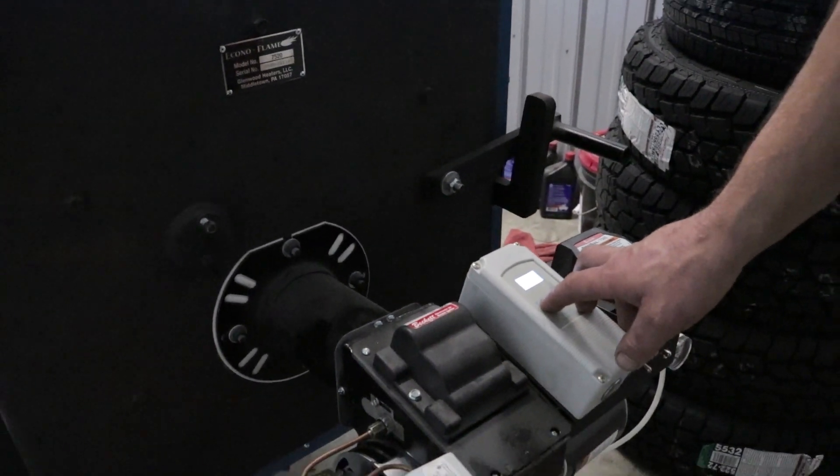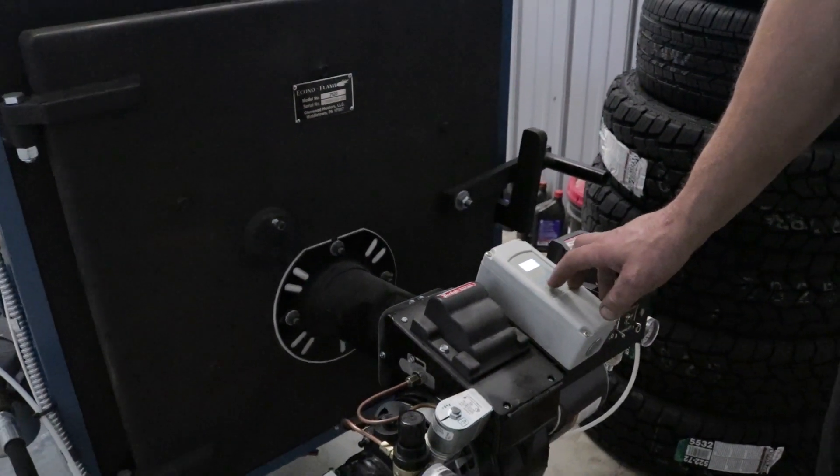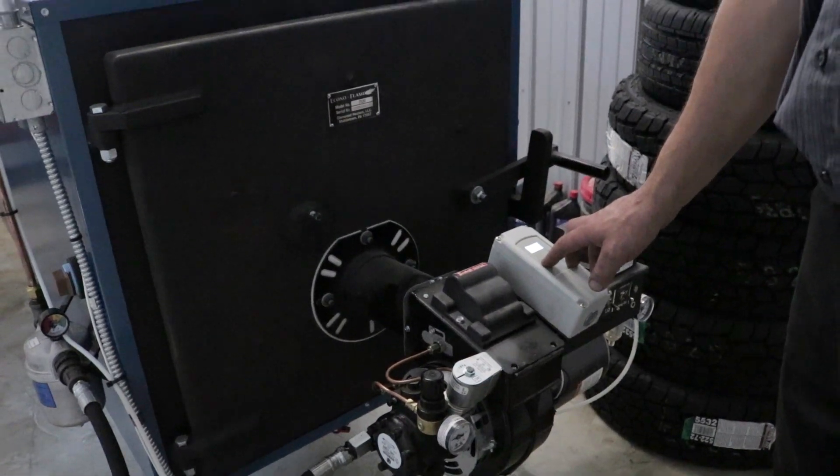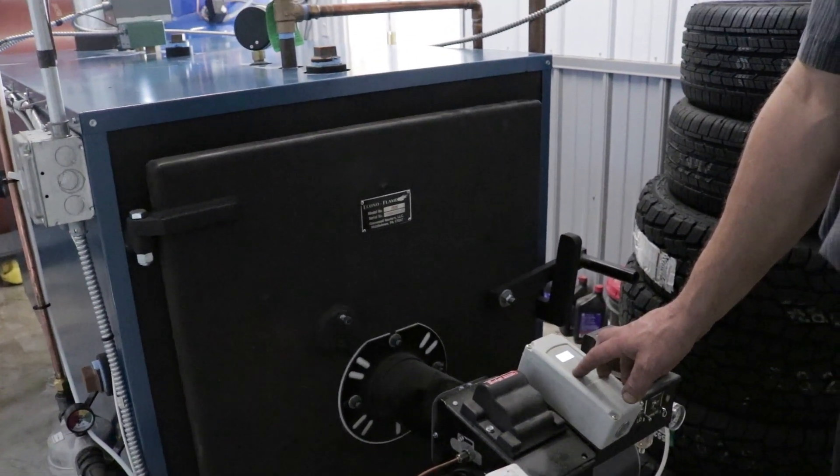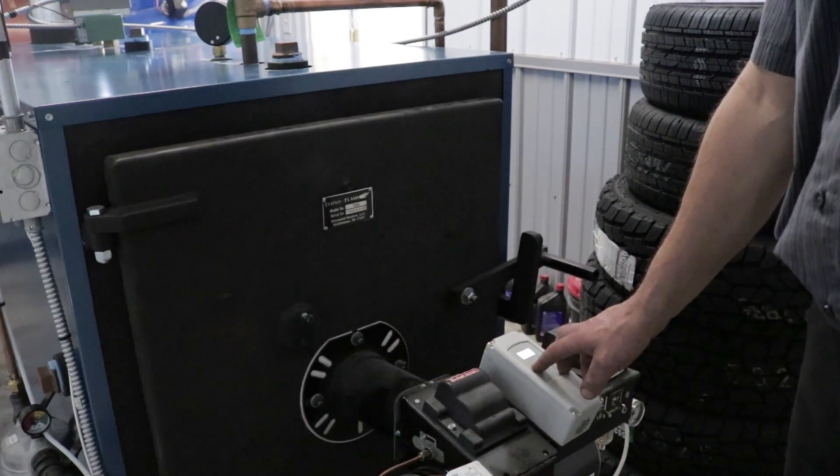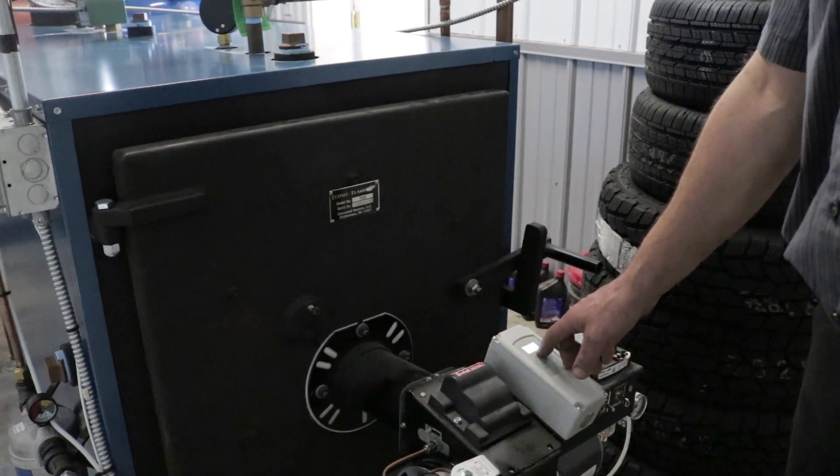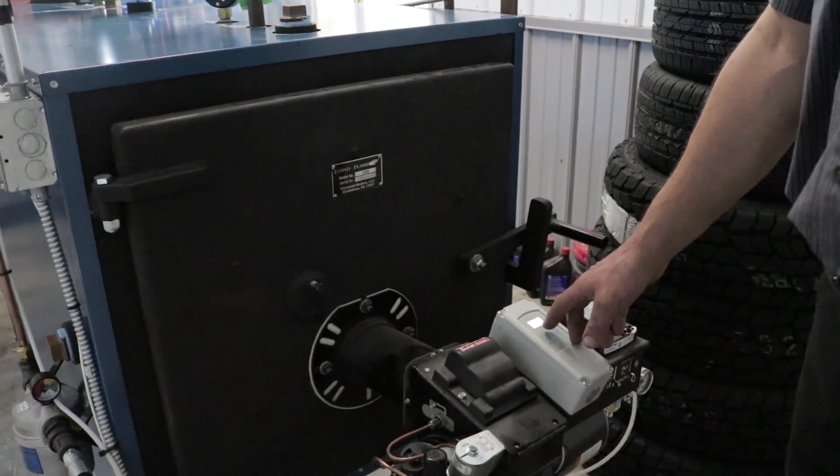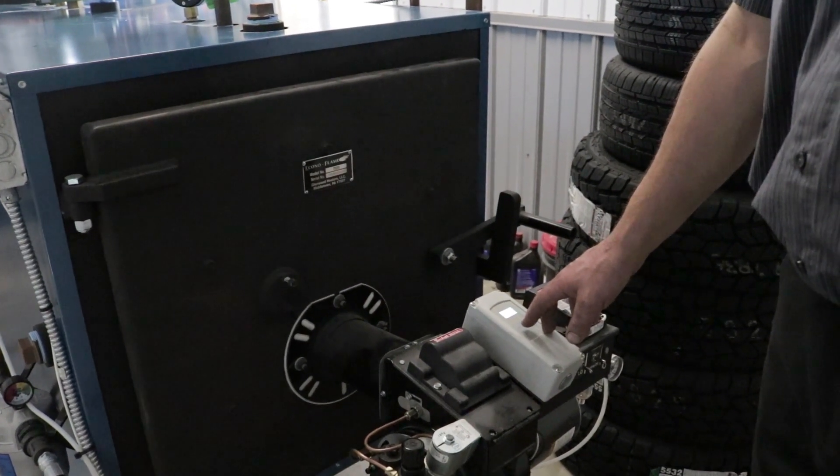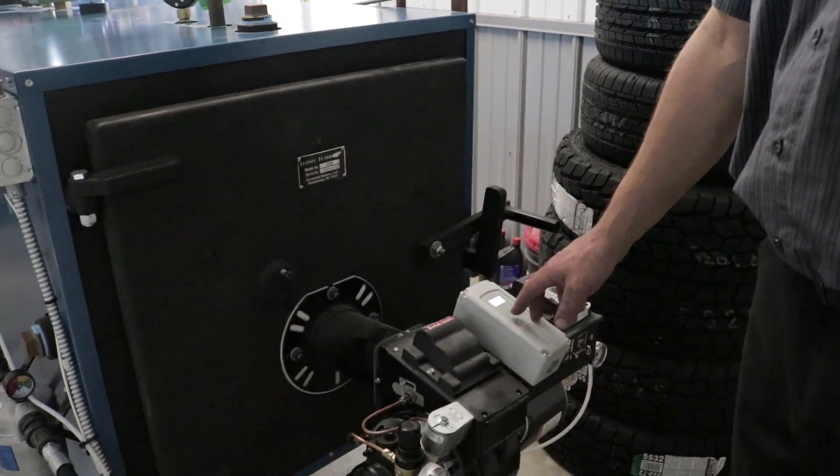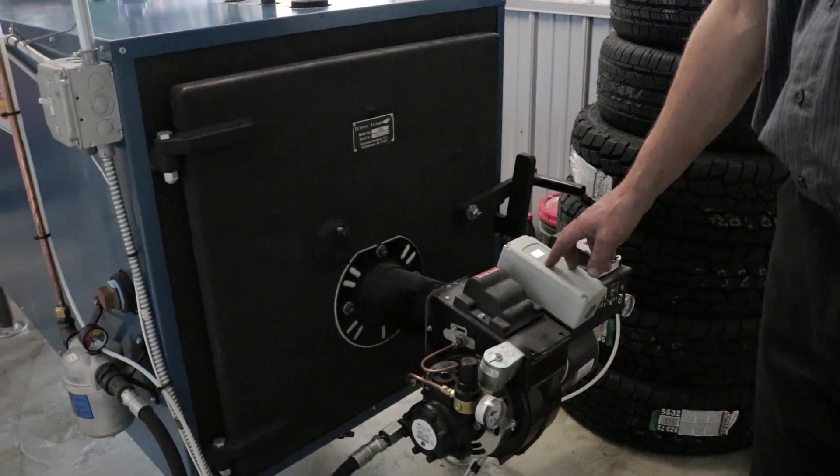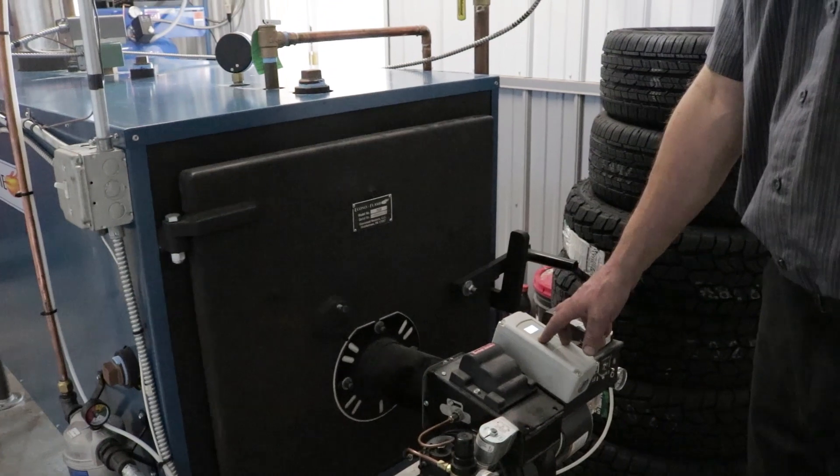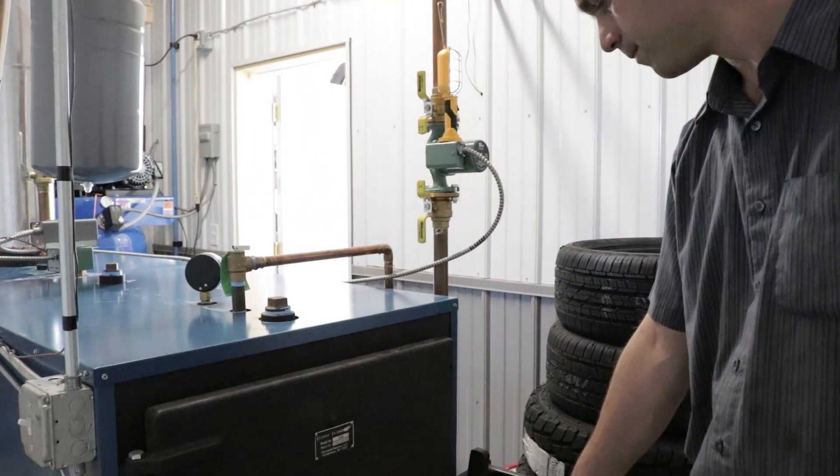This thermostat controls the whole function of the burner. If the oil is not warm enough, the burner will not be able to run. Here we have it set at 160 degrees—it will not be able to run unless the oil temperature is at 160. If the oil temperature reaches 180, then the preheater shuts off.